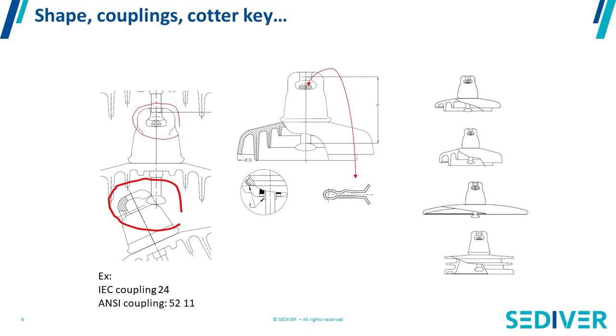And you have two different standards worldwide which are covering those definitions. In IEC you have couplings which have numbers like 16, 20, 24. In ANSI, the American standard, the couplings are reference 52-5, 52-11. In the standard you have description of every dimension of every socket and every ball of every type of coupling. And unfortunately IEC and ANSI are not compatible. So if you have insulators which are used on the American market, you're going to use a shape of socket and ball that is different from what is being used anywhere else around the world, which is using IEC. So coupling is a word to describe the style of connection between two insulators in order to build an insulator string.